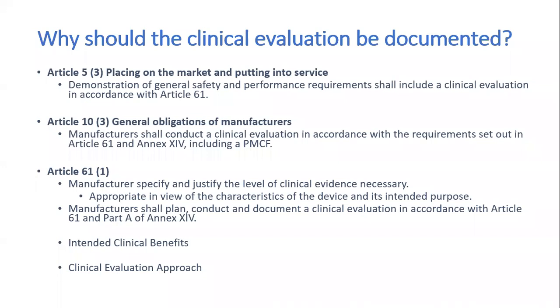Now, why should clinical evaluation be documented? So as per Article 5.3, we have to place on the market and put into service. So we have to demonstrate the compliance of our data as per the GSPR checklist, which is Annex 1 of EU MDR 2017-745, which is given in Article 61. So we have to see to it that we are compliant with general safety and performance requirements, and that is as per Article 61. And as per Article 10.3, the general obligations of manufacturers.